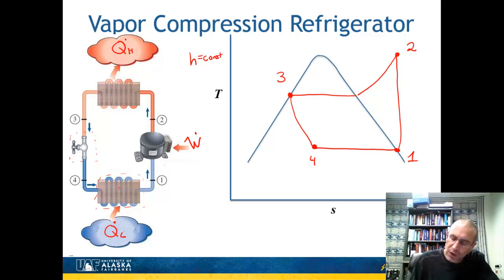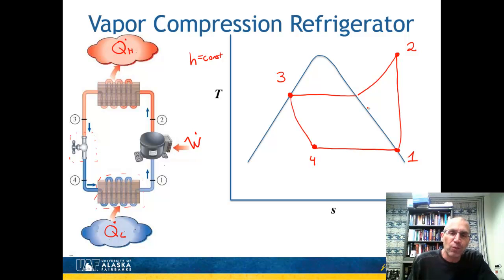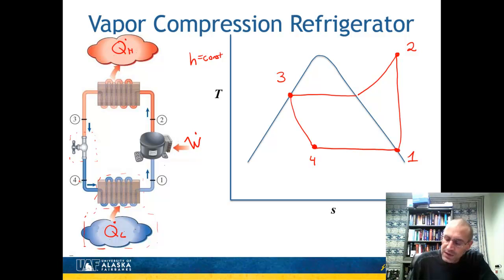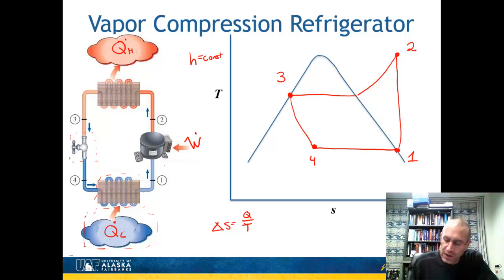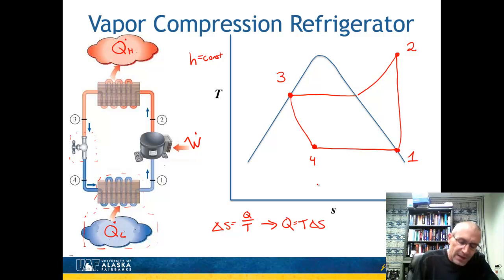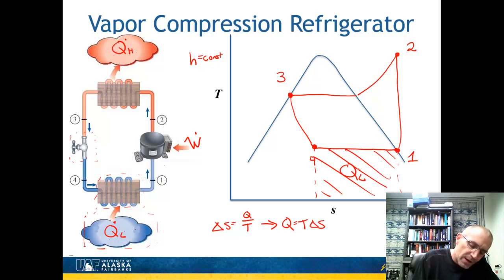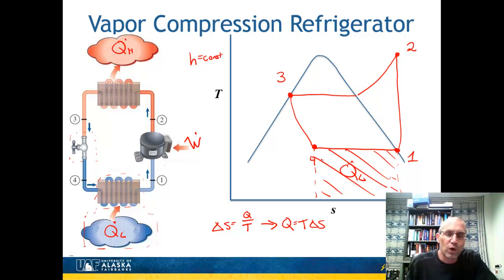The process from 4 to 1 assumes no pressure drop in the freezer box. An important point: what we really care about is Q_L — how much heat we can remove from the refrigerated space between points 4 and 1. Since delta S equals Q over T at constant temperature, Q equals T times delta S. This means the area under the 4-to-1 process on the TS diagram represents the cooling capacity — that area is Q_L. To optimize the cycle, we want to increase this area without increasing the work requirement.